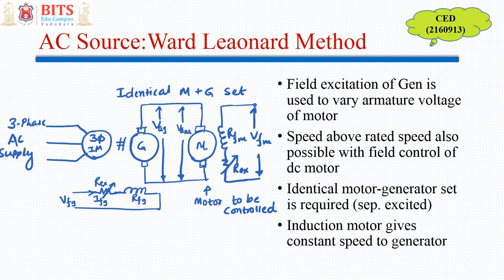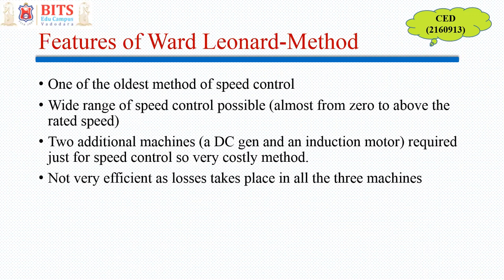This method requires an identical motor-generator set that is separately excited, and the induction motor gives constant speed to the generator. This is one of the oldest methods of speed control — it was used where speed control was invariably required and cost was not an issue. A wide range of speed control is possible, from minimum to above rated speed — that is the beauty of this method.